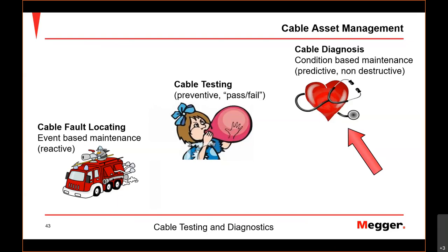Judge joints, how good they are. If you have some weak spots in joints, you could just go and repair the joints to get your network system running stable again, and avoid outage times. Also a very nice thing with the joints: if you find that they have problems, you can repair them before they actually fail. So you can do that under scheduled and planned conditions, so customers don't see any outage, they're supplied some other way.